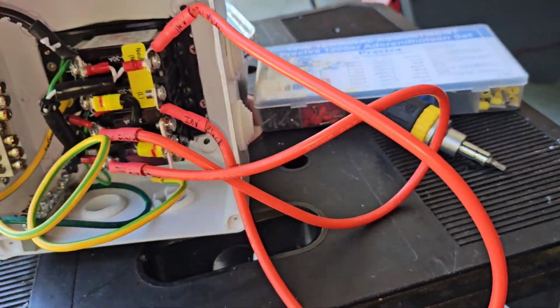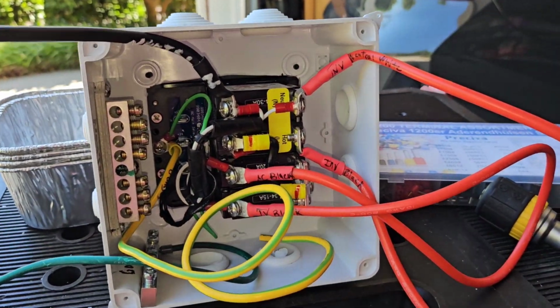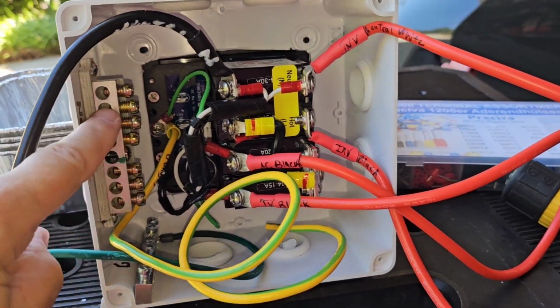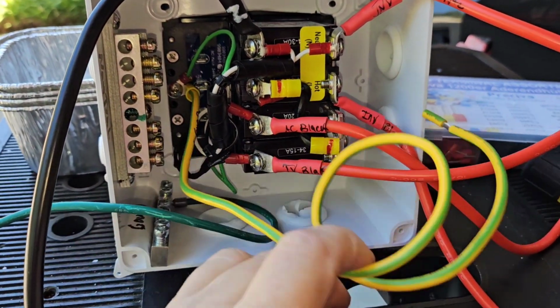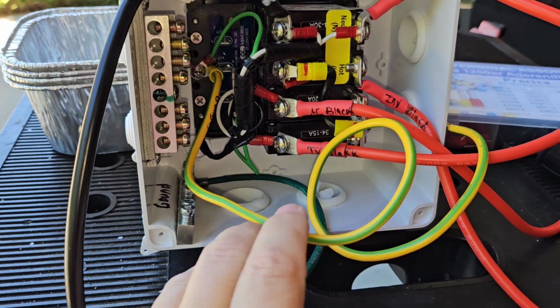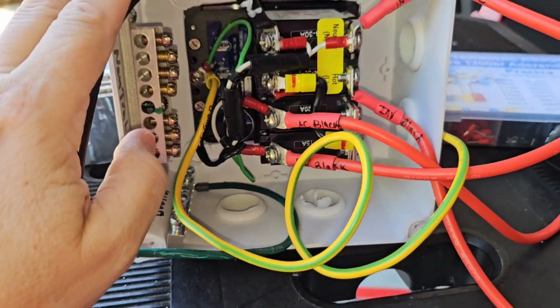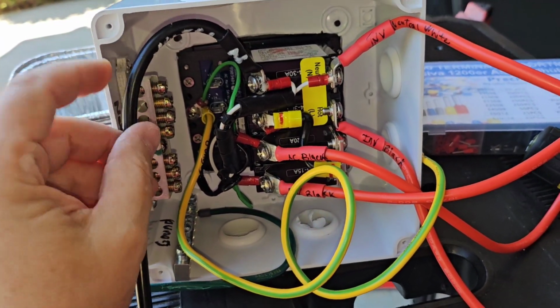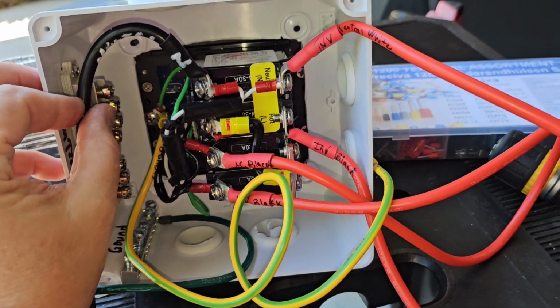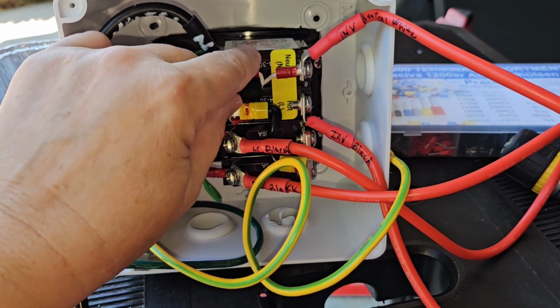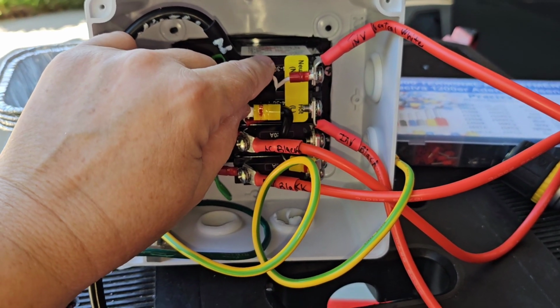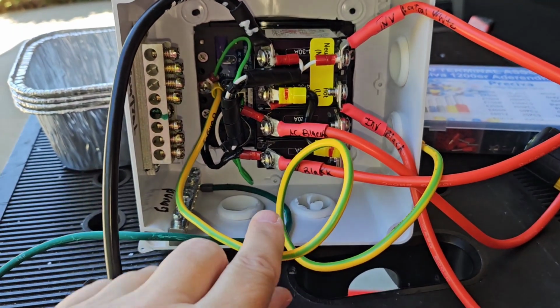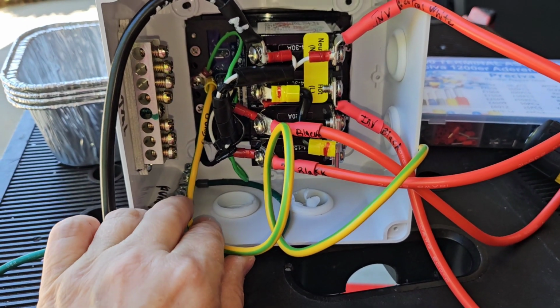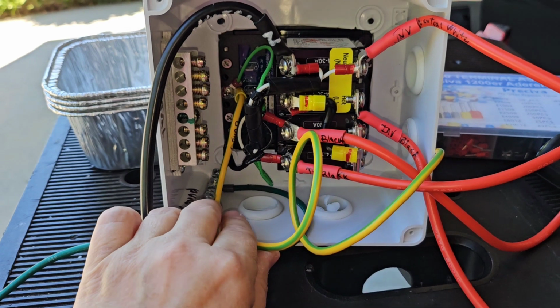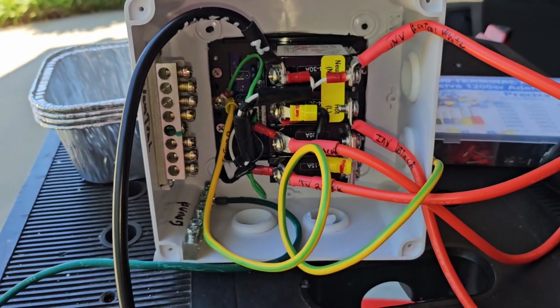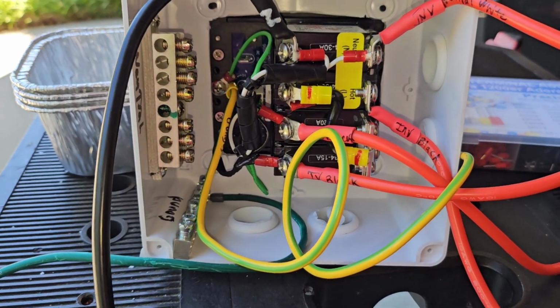And here is the back side. I still have to hook up my neutral bar to this neutral bar, my ground wire to the ground bar down here. That links this ground bar to the 30 amp main breaker where the inverter output comes in, and this ground goes to the ground bar that connects all the grounds to this unit and the circuit grounds.